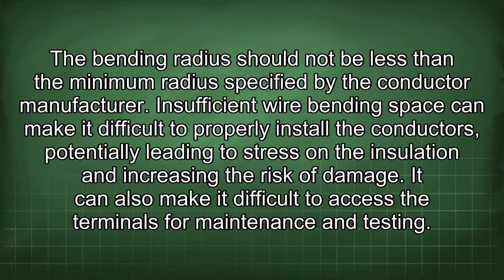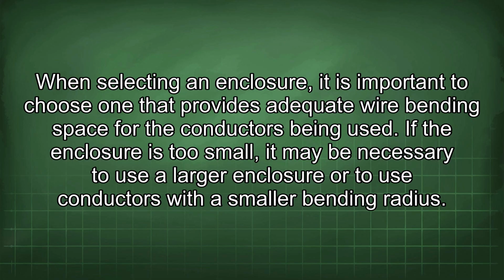Insufficient wire bending space can make it difficult to properly install the conductors, potentially leading to stress on the insulation and increasing the risk of damage. It can also make it difficult to access the terminals for maintenance and testing. When selecting an enclosure, it is important to choose one that provides adequate wire bending space for the conductors being used. If the enclosure is too small, it may be necessary to use a larger enclosure or to use conductors with a smaller bending radius.